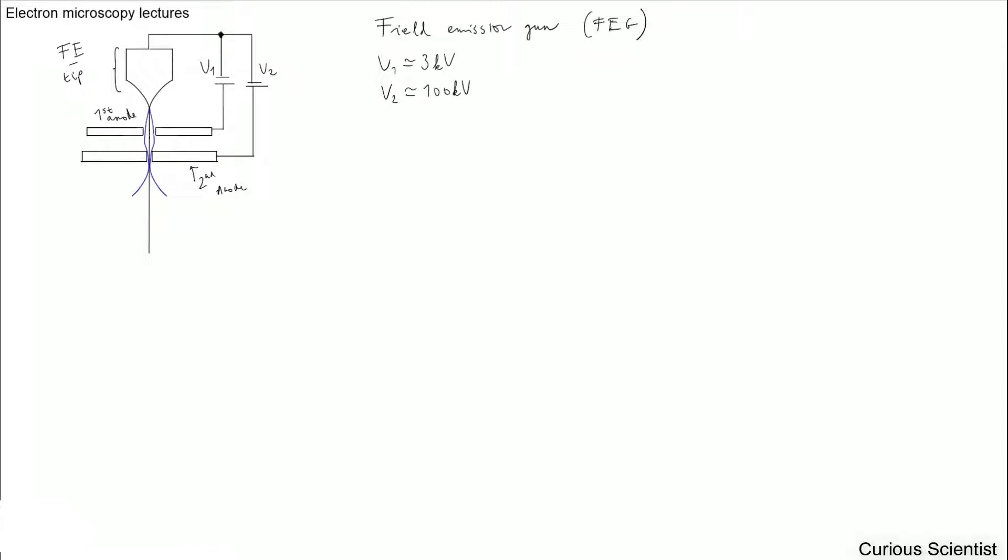So what's the difference between the previous guns and this current gun? So the previous guns, the tungsten guns and the lanthanum hexaboride guns, these both work with thermionic emission. So basically you heat up the piece of material, which is the tungsten filament or the lanthanum hexaboride crystal, and apply a field which will pull out the electrons.